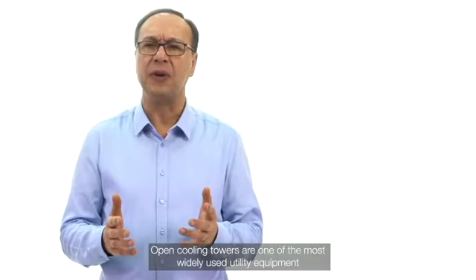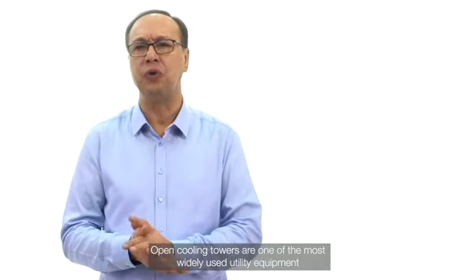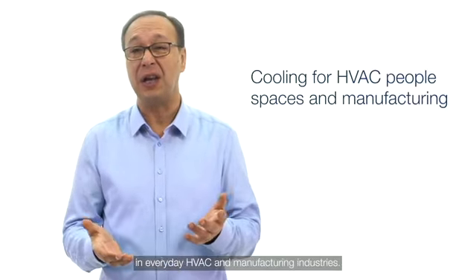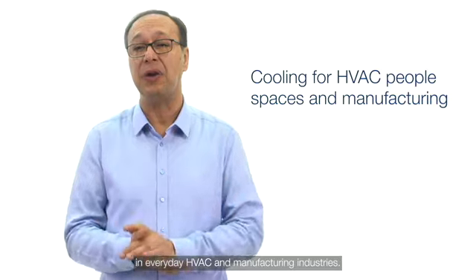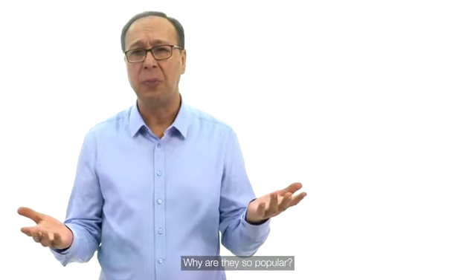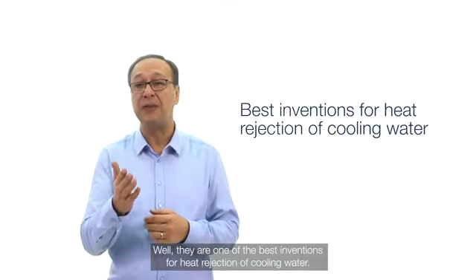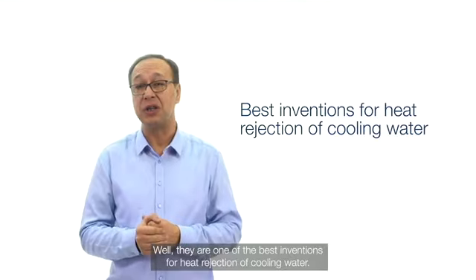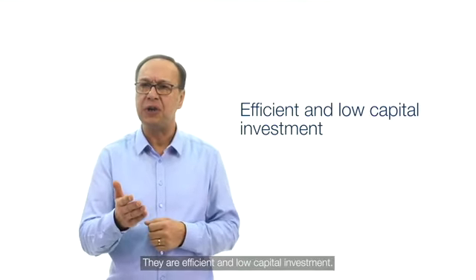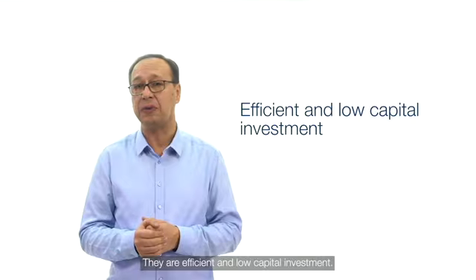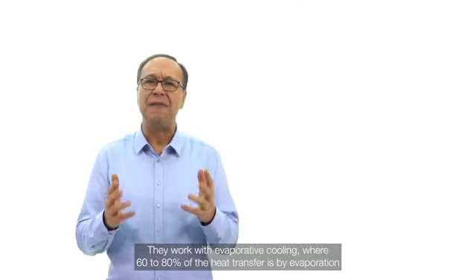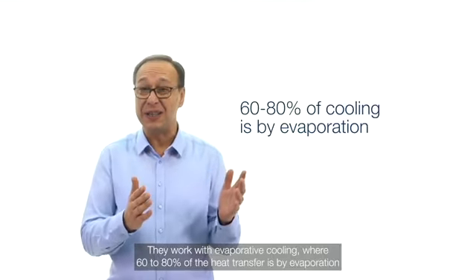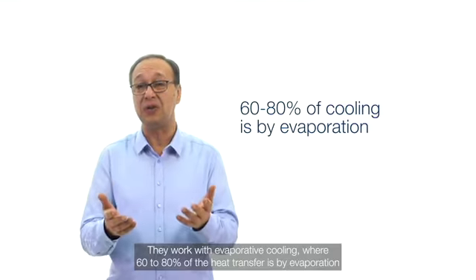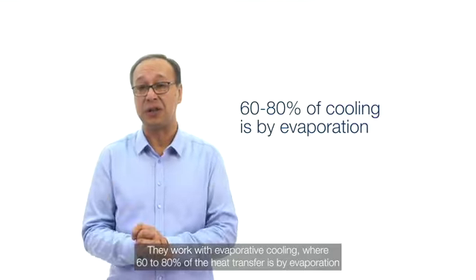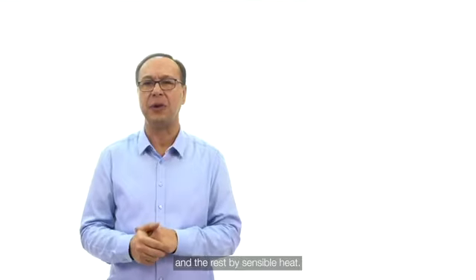Open cooling towers are one of the most widely used utility equipment in everyday HVAC and manufacturing industries. Why are they so popular? Well, they are one of the best inventions for heat rejection of cooling water. They are efficient and low capital investment. They work with evaporative cooling, where 60 to 80% of the heat transfer is by evaporation and the rest by sensible heat.